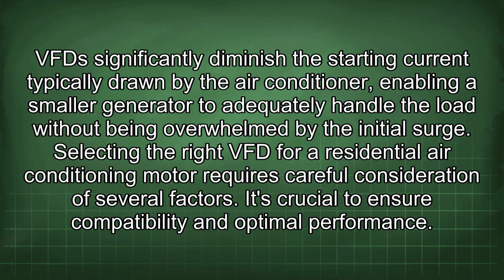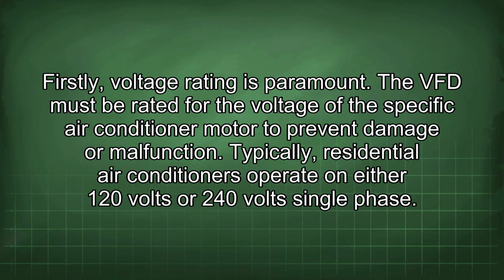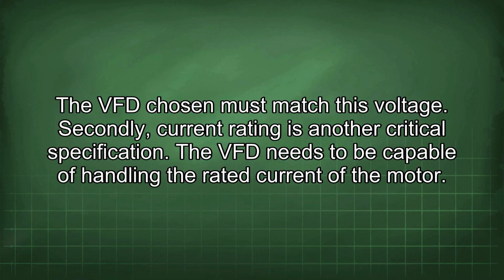Selecting the right VFD for a residential air conditioning motor requires careful consideration of several factors. It's crucial to ensure compatibility and optimal performance. Firstly, voltage rating is paramount. The VFD must be rated for the voltage of the specific air conditioner motor to prevent damage or malfunction. Typically, residential air conditioners operate on either 120 volts or 240 volts single phase. The VFD chosen must match this voltage.